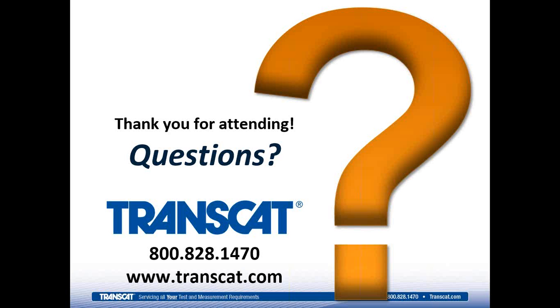Yeah, what you want to look for in any of the industries that you work in is your source documents that give you guidance as to what performance your company has to have against national or international standards. And what you want to look for in there is what the requirements are for calibration. Search on keywords like calibration, metrology, suitability, things like that, to see what it says about what your requirements are for selecting the right instrument for the job effectively. And so that's what I did in these other standards, is I looked for the term suitability. And every industry has its own guidance documents or requirements that it must adhere to. So I would suggest you pull that up and do a search on it, see if you can find anything related to that, or find the section related to calibration and what the requirements are.